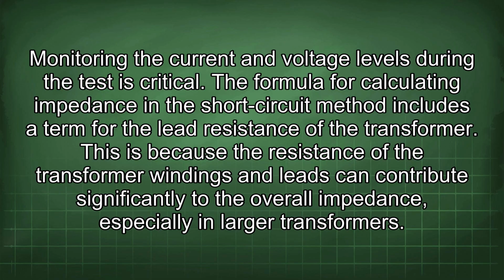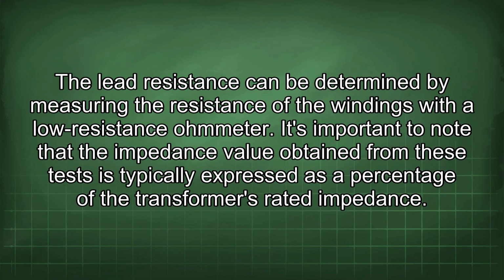The formula for calculating impedance in the short-circuit method includes a term for the lead resistance of the transformer. This is because the resistance of the transformer windings and leads can contribute significantly to the overall impedance, especially in larger transformers. The lead resistance can be determined by measuring the resistance of the windings with a low-resistance ohmmeter.